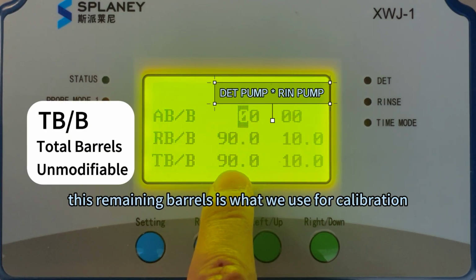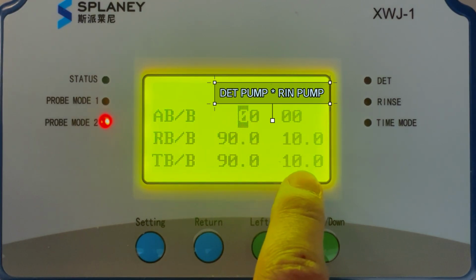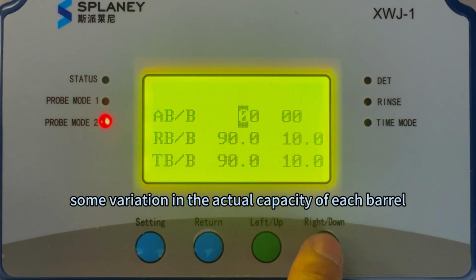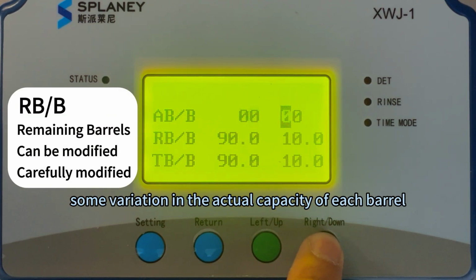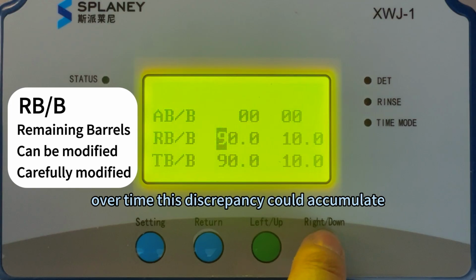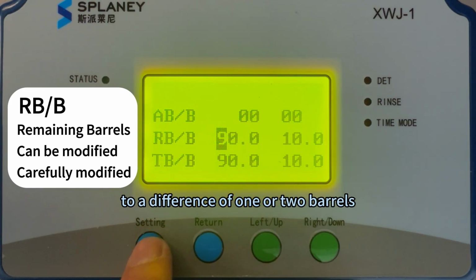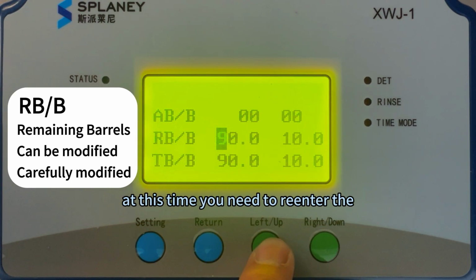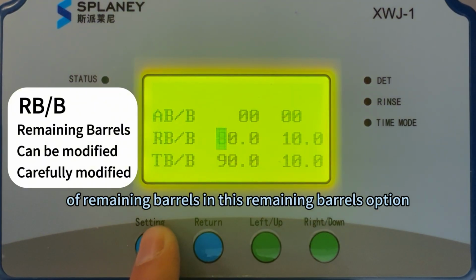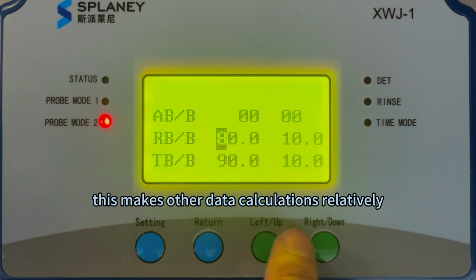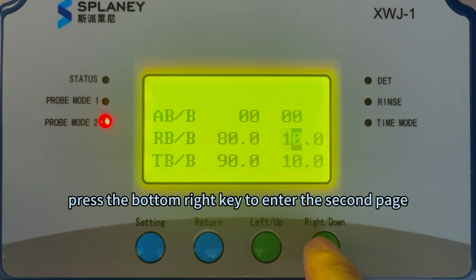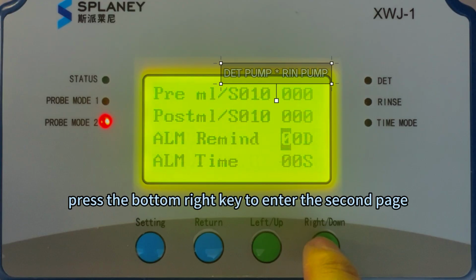Then this remaining barrels is what we use for calibration. Because there might be some variation in the actual capacity of each barrel, over time this discrepancy could accumulate to a difference of 1 or 2 barrels. At this time, you need to re-enter the current number of remaining barrels in this remaining barrels option. This makes other data calculations relatively much more accurate. Press the bottom right key to enter the second page.